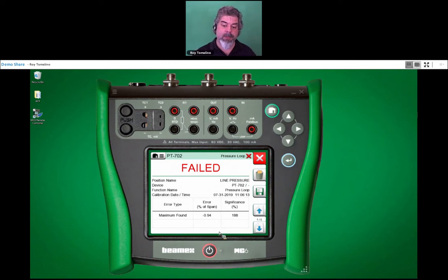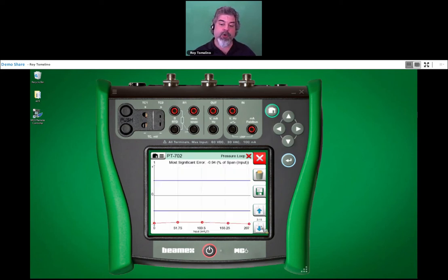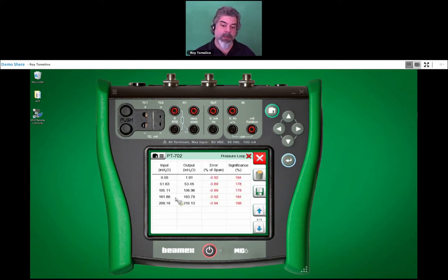Oh, I failed. All right, Ned. Fine. So I'm totally out of the blue. I really am out of the blue. Here's all my numbers. I was almost a 1% of span out all the way across, and my significance reflects that as well. I'm almost double what I was allowed.